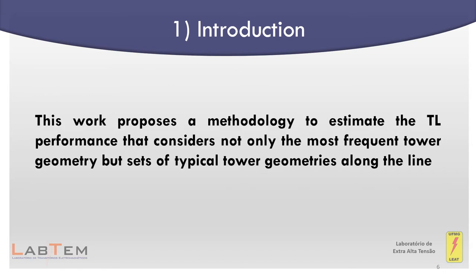This work proposes a methodology to estimate the transmission line performance that considers not only the most frequent tower geometry, but sets of typical tower geometries along the line. The proposed methodology is applied to a real 230 kV line and the results are compared with those obtained using the conventional methodology.